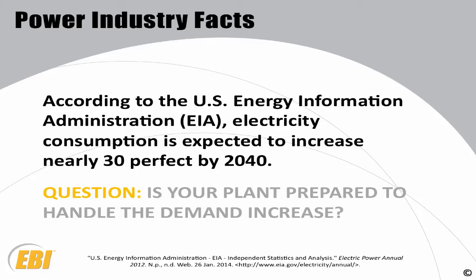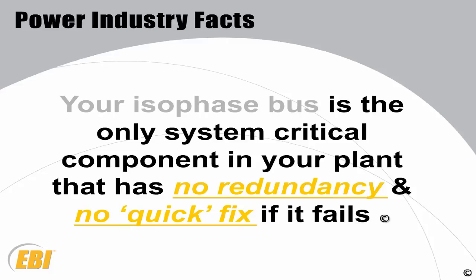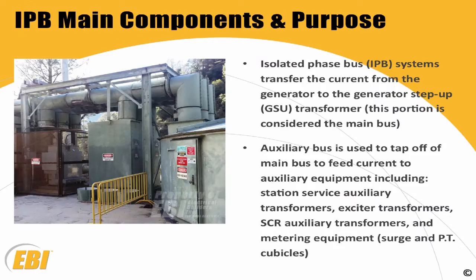According to the U.S. Energy Information Administration, electricity consumption is expected to increase nearly 30% by the year 2040. Is your plant prepared to handle this? Your isophase goes between the generator and your step-up transformer. It's the only thing that carries the current. It has no redundancy, and there's no quick fix if you have a problem.